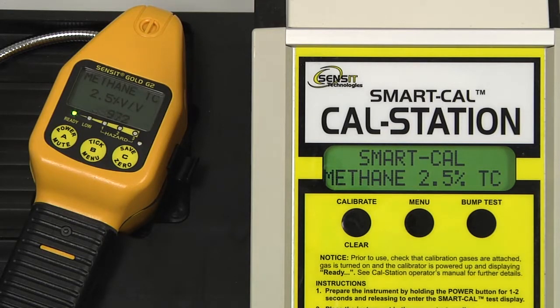On the display of the instrument itself, we'll have a number at the bottom of the screen. This number is the raw output of the sensor and is useful for troubleshooting if any issues should occur. After each calibration has passed, saved will be displayed on the instrument and passed will be displayed on the cal station.